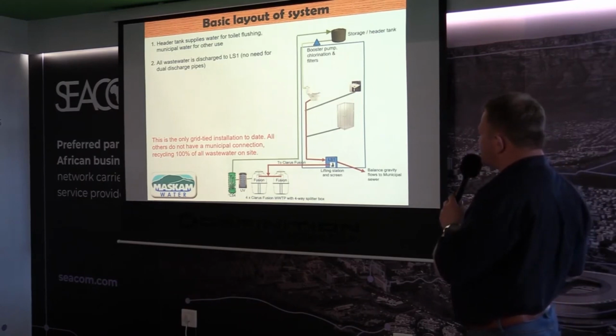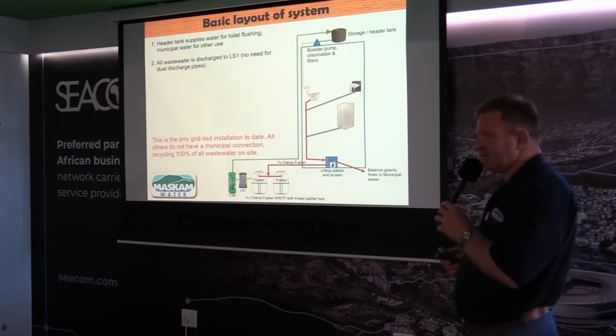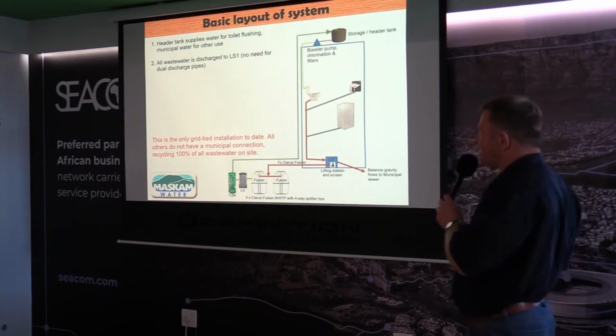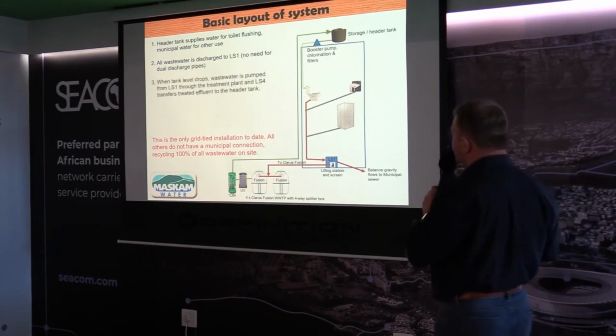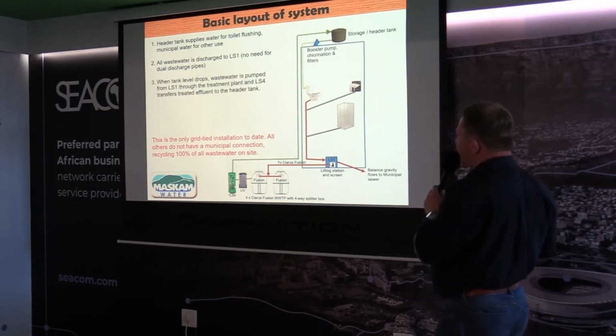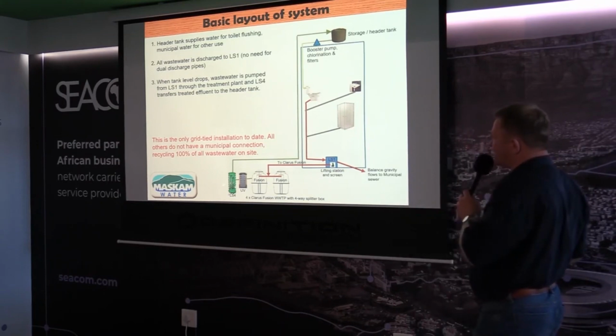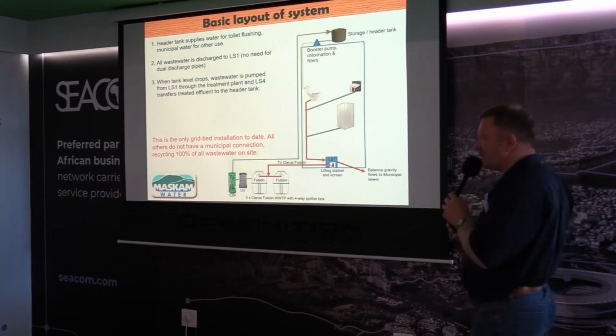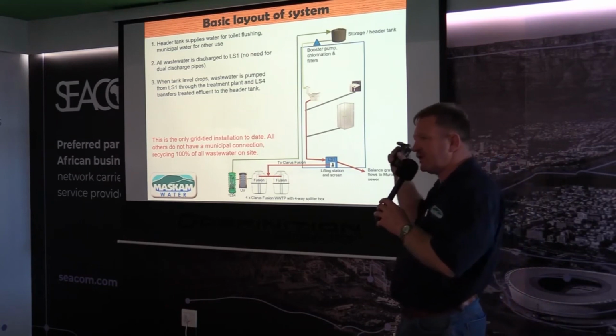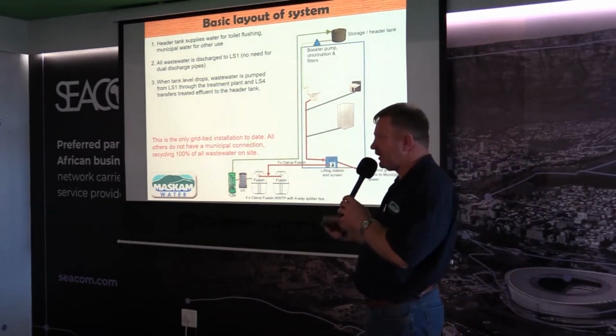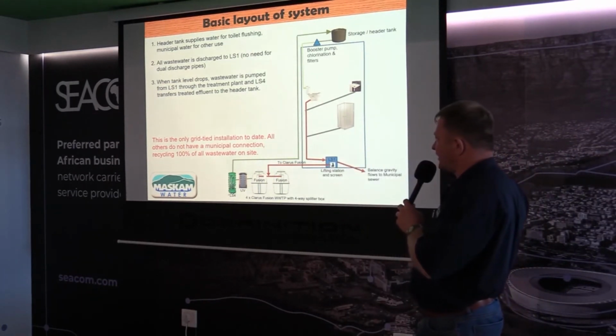All wastewater is discharged to lifting station number 1 in the basement. And if that tank has sufficient water, the untreated sewage will simply overflow to the municipal line. When the tank level drops to 80%, it demands wastewater from lifting station, or treated effluent from lifting station 4. Lifting station 4 in turn demands raw sewage from lifting station 1. We literally pump the sewage through the ceiling of the ground floor, through to the treatment plants in the quad.